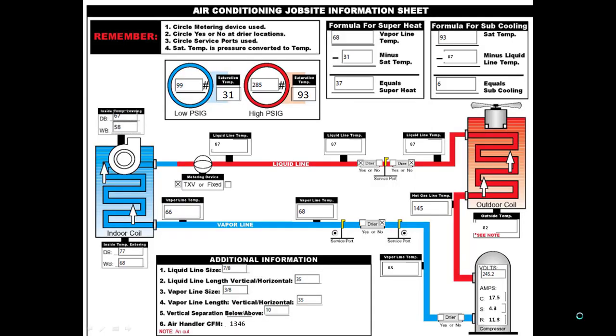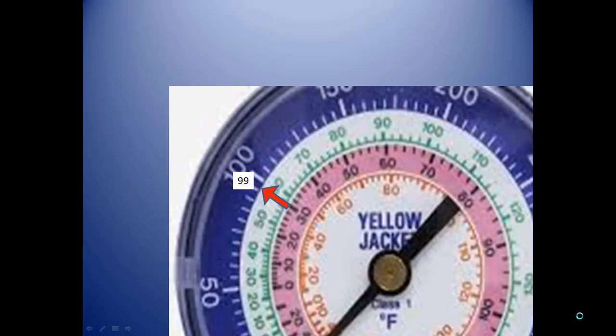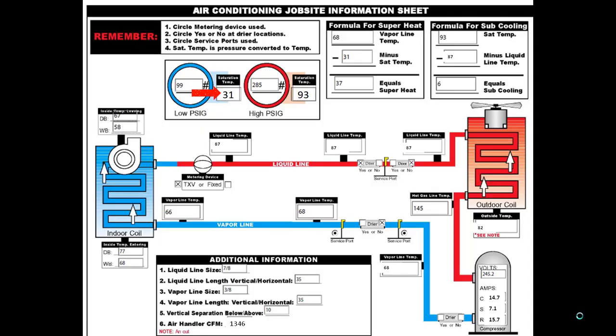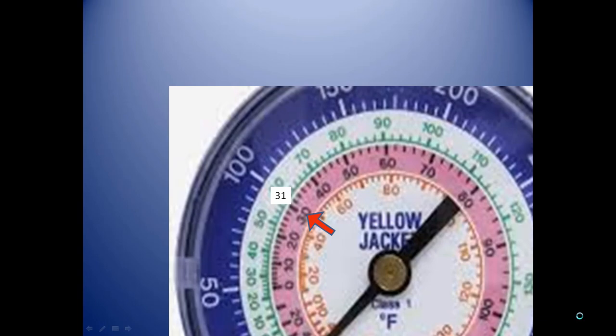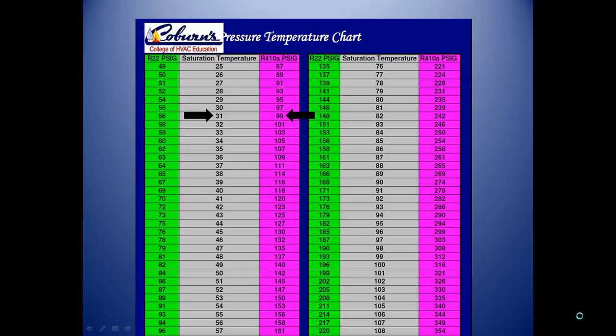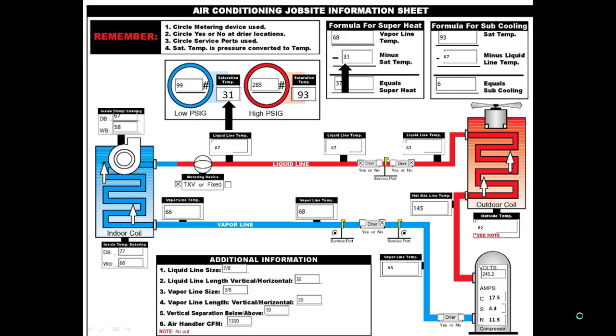On the second form, we need the suction line pressure. That can be taken right off the gauge manifold. We also need the saturation temperature, which could also be gotten right off the gauge manifold, or you can go to the pressure temperature chart and convert pressure into saturation temperature. We'll place those readings right here on the job site information sheet.